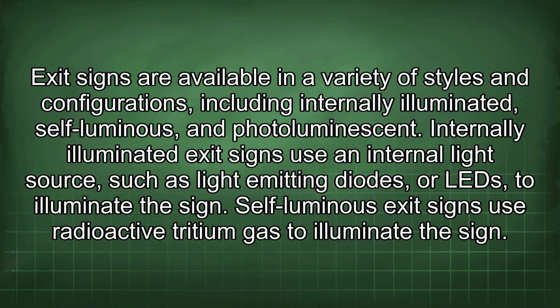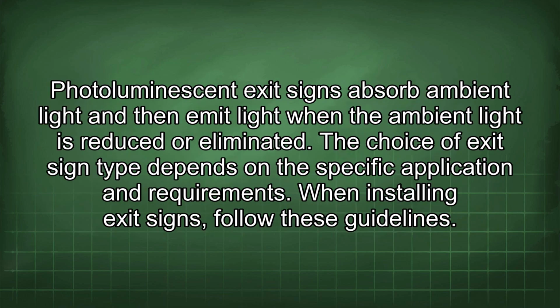Exit signs are available in a variety of styles and configurations, including internally illuminated, self-luminous, and photoluminescent. Internally illuminated exit signs use an internal light source, such as light-emitting diodes or LEDs, to illuminate the sign. Self-luminous exit signs use radioactive tritium gas to illuminate the sign. Photoluminescent exit signs absorb ambient light and then emit light when the ambient light is reduced or eliminated. The choice of exit sign type depends on the specific application and requirements.